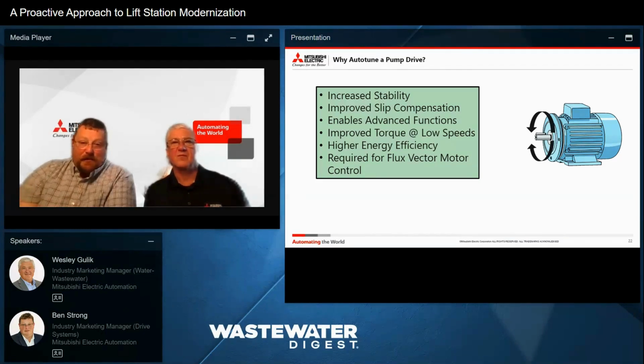So, other reasons to auto-tune a pump drive: increase stability. Well, what does that mean? It means the drive's going to hold a constant speed and it's going to be more accurate. Does that matter as much in lift stations? No, but that's one of the benefits. Improve slip compensation, so it's going to run with less energy. We mentioned it enables all the enhanced functions. We didn't even talk about all the different things a VFD could do. We're going to run out of time.